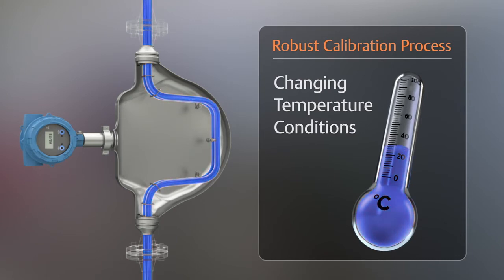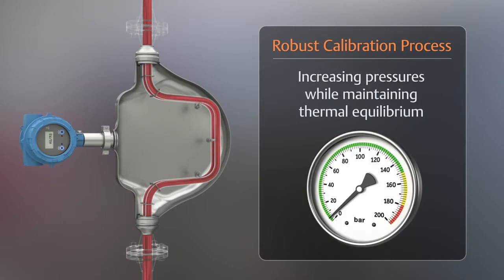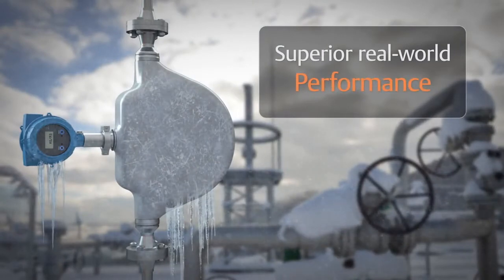The meter is also calibrated for temperature, starting at room temperature and then at elevated temperatures. The calibrations are also conducted with increasing pressures, while maintaining thermal equilibrium between the fluid, the meter, and the environment. This allows the meter to achieve superior real-world performance.